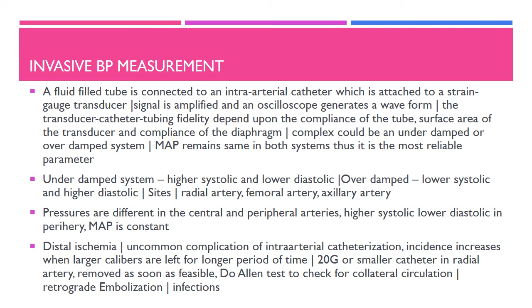To summarize, the take-home message is, if you are measuring the blood pressure indirectly, make sure that the width of the cuff is at least half the circumference of the limb. And if you are measuring the pressure invasively, always rely upon the mean arterial pressure. The NIBP is not as reliable as the IBP, but that is the one which is most frequently used.